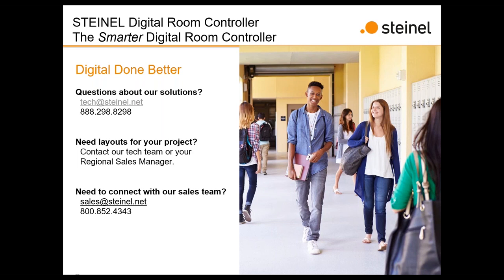Let's do one more question. Can this be used for fire alarm or security input for the whole system? Good question. There's a contact input, we previously called it a time clock input, but that input can be used for various other things, one of which can be a fire alarm. Whenever you're programming the app, you create a sequence of operation for when that contact closure happens. For example, you might want the lights to go to full bright whenever that contact closure happens, and disable the switches, disable the occupancy sensors, and so on. You simply create the sequence of operation for the contact closure input, so now whenever it receives that input, it performs the action you've created.